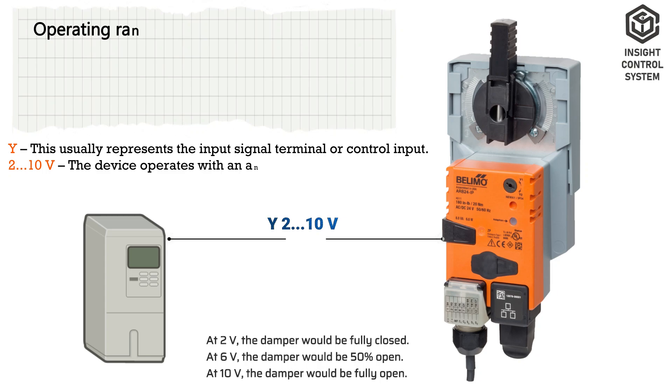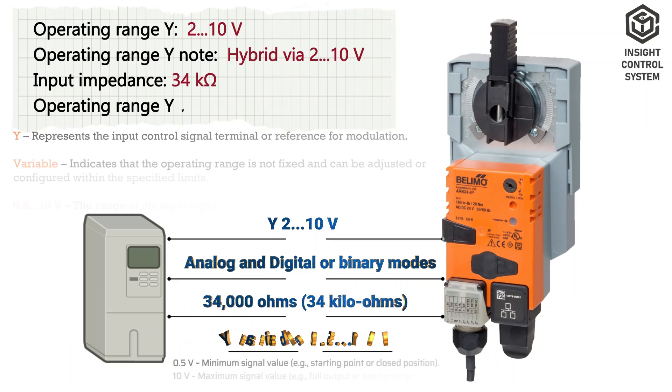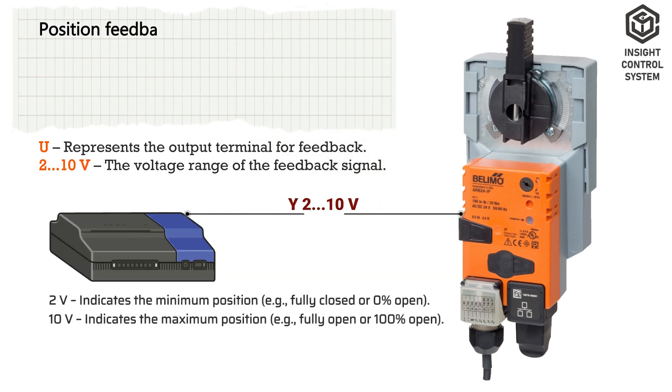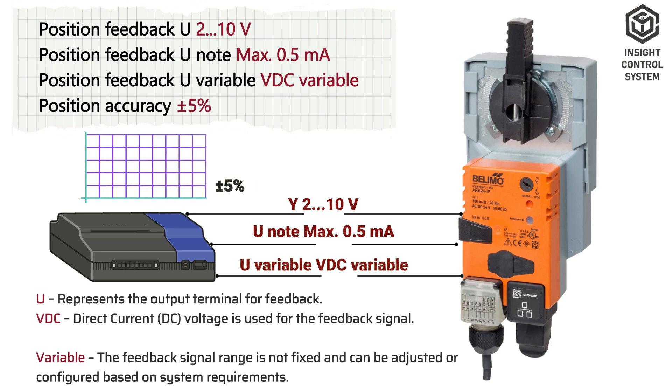Control Data. Operating range Y is 2 to 10 V. Operating range Y note for hybrid is 2 to 10 V. Input impedance is 34 kΩ. Operating range Y variable is 0.5 to 10 V. Position feedback U is 2 to 10 V. Position feedback U note is maximum 0.5 mA. Position feedback U variable is VDC variable. Position accuracy is ±5%.